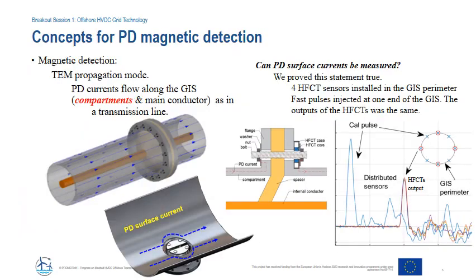A technique based on magnetic detection of PD signals in the low frequency range, as compared to the UHF range, has been proposed and reported in D15.3 and D15.5 within Work Package 15. This alternative technique relies on the concept that in the TEM propagation mode, PD currents flow along the GIS compartments and main conductor as in a transmission line. If so, then such currents can be picked up by magnetic sensors.